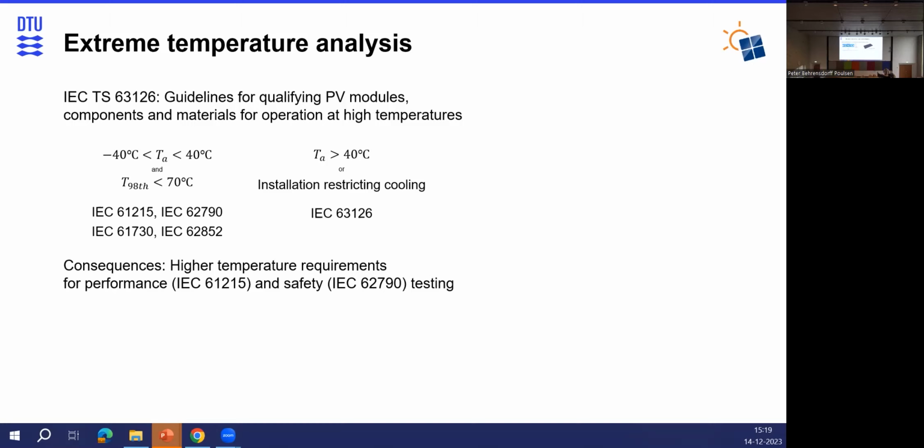But we knew from our experience that actually not all our systems are getting operating values above 70 degrees Celsius. And we wanted to look into, well, how does that compare? Do all these systems stay below these 70 degrees? Can we maybe influence some change in the standard so that this extensive testing is not necessary for all systems?